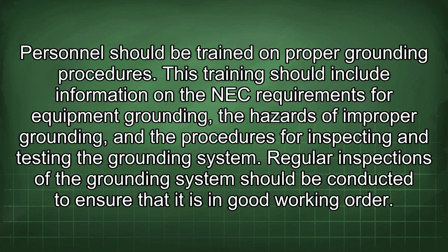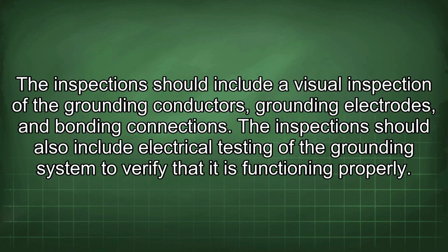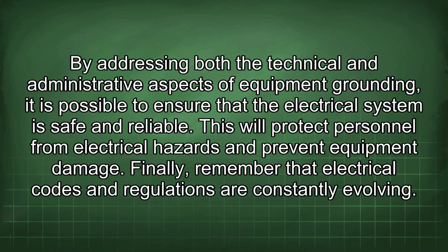Regular inspections of the grounding system should be conducted to ensure that it is in good working order. The inspections should include a visual inspection of the grounding conductors, grounding electrodes, and bonding connections. The inspection should also include electrical testing of the grounding system to verify that it is functioning properly. By addressing both the technical and administrative aspects of equipment grounding, it is possible to ensure that the electrical system is safe and reliable. This will protect personnel from electrical hazards and prevent equipment damage.